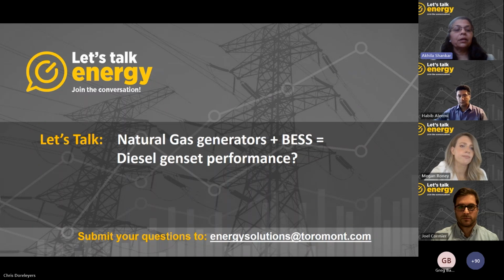Hey, good question, Megan. So when we say transient performance of a generator set, we're talking about the voltage dip, the frequency dip, and the time it takes to recover to rated values when a load is applied on the gen set. For standby or peak shaving market, the diesel-like performance characteristics that are needed are fast starting, block load acceptance capability, rapid recovery to rated values, and steady state stability capabilities.